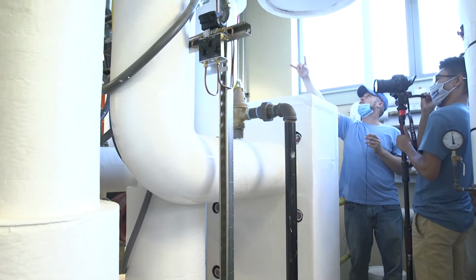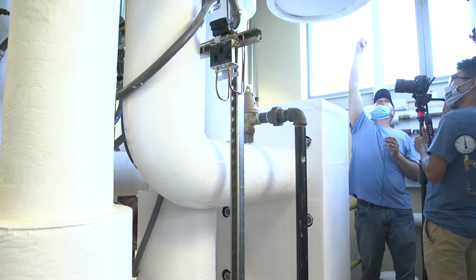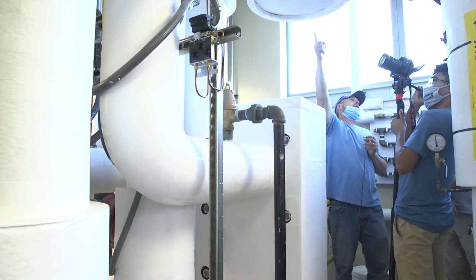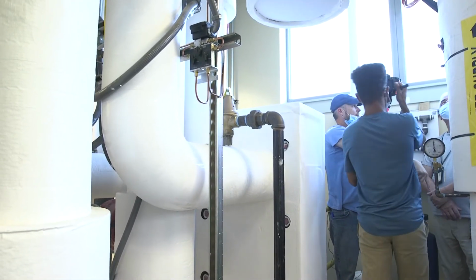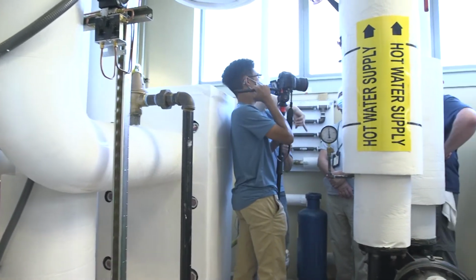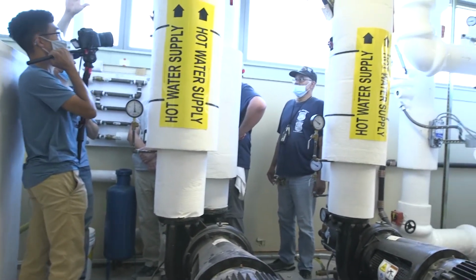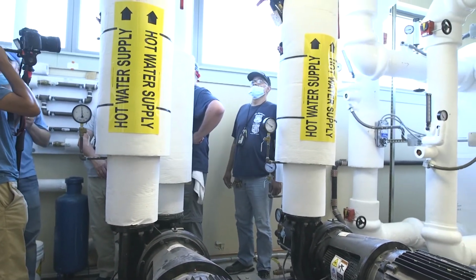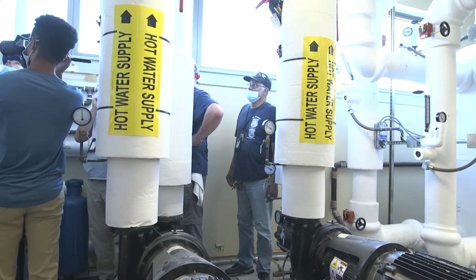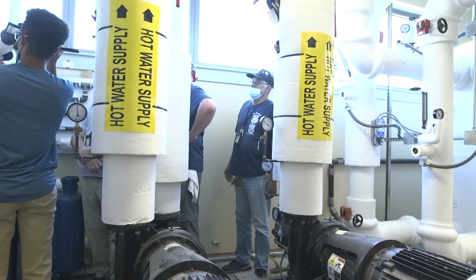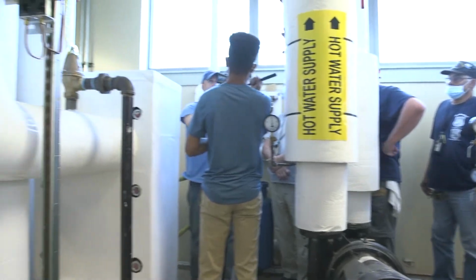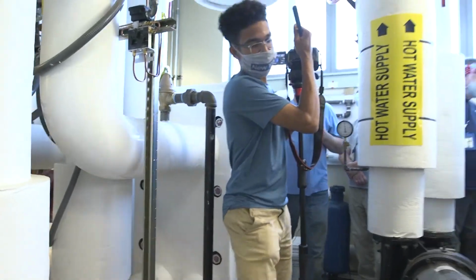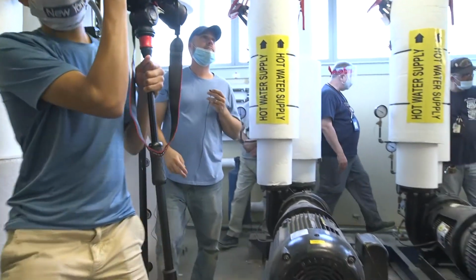So if you were to shut these valves, the water would come this way and go out to your system, go into the suction side of your pump. And then this would send primary hot water straight to the building. So if these ever had to come offline, you open these valves up, you'll have heat. You can go back out. On the chill water, you have the same situation.